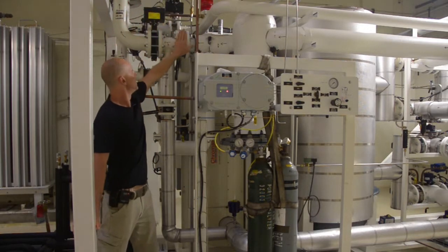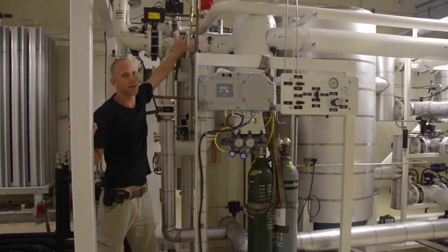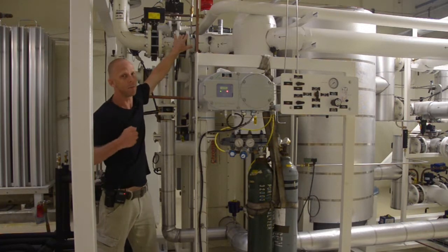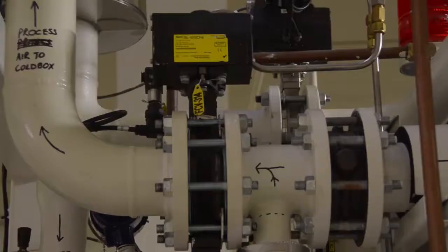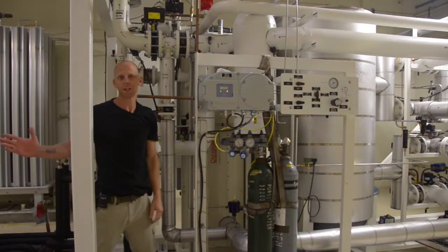And our process air moves through these 2 valves and up through this line and into our cold box. Okay, this is a manual valve. It's just an extra level of safety that we can manually make sure that the cold box is closed to the process air until certain conditions are met. And this is an automatic trip valve. This valve, flow control valve 314, will only open and allow process air through into our cold box if our lube oil system is running.